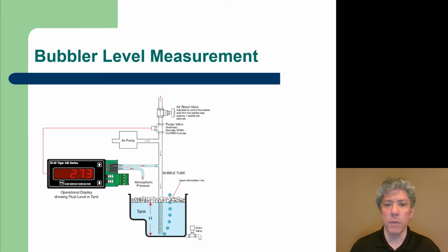There's also a purge valve here. If you open that up, what you're doing is allowing the normal operation of the system, but if you close it, that'll force all of the air down through the bubble tube and purge it out. If any liquid ends up in the tube, it can throw off the reading, and so it's important to occasionally purge the tube in order to take a proper measurement.